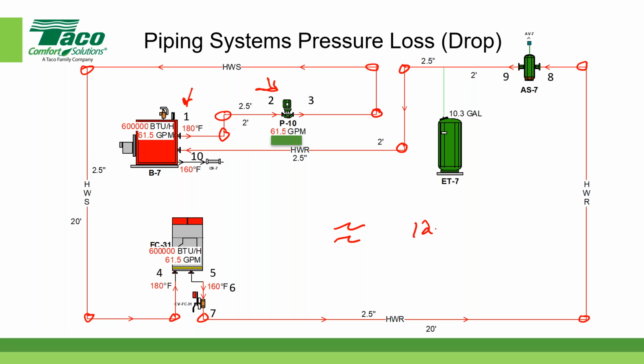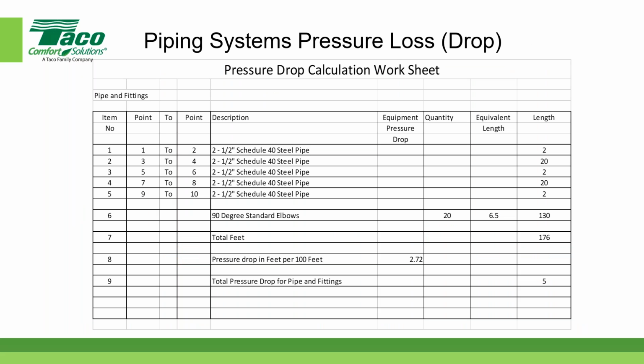If I multiply that times 1.5, which is a reasonable factor, that's 18. So I'm going to round it off and say I've got 20 elbows. So you see the methodology. I counted 12. I multiplied by 1.5 because I wanted to have some additional allowance for fittings. Then I rounded it off, and that's what I put in my table over here. So I put in 20 on my table.